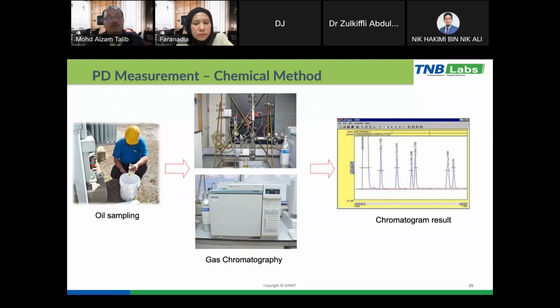So the PD measurement through the chemical method for the power transformer: normally the big power transformer is filled with oil. So we go to the site, take the oil sample from the transformer, and then we bring it to our lab. We use GC, gas chromatography. We have a gas extractor, so we extract the gas from the oil, and then we pass it through this GC. In the GC we have two sensors, FID and TCD, and these sensors will pick up the chromatograms, and through this signal, through this peak, it will tell what are the gases dissolved in the oil.